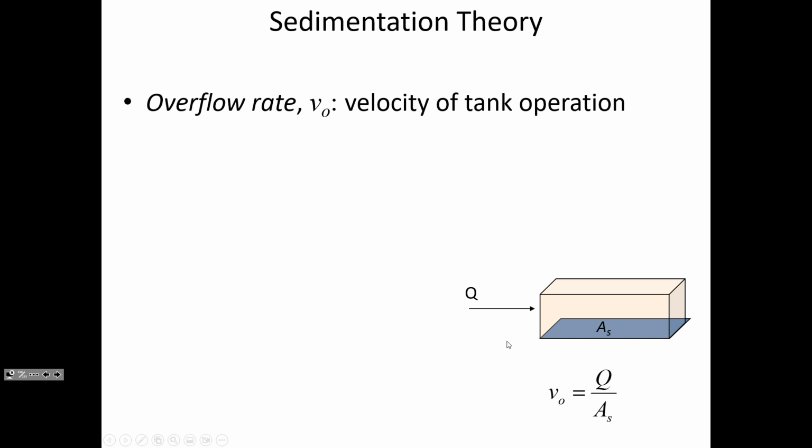Okay, so if Q stays the same and we double the volume, what does that do to the residence time? Double it. I mean, this just makes sense. You got the same flow rate coming into the tank. If the tank is twice as big, then the water's going to spend twice as long in the tank before it goes out. But what I'm saying is that the settling performance isn't changed by the fact that the water is spending twice as long.